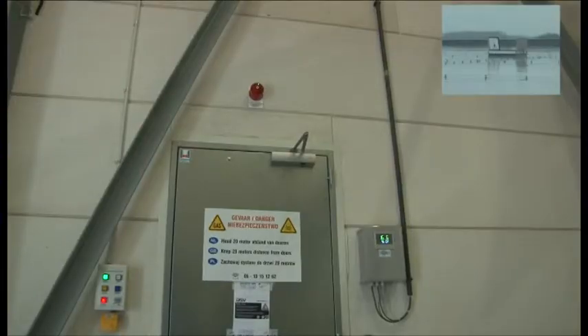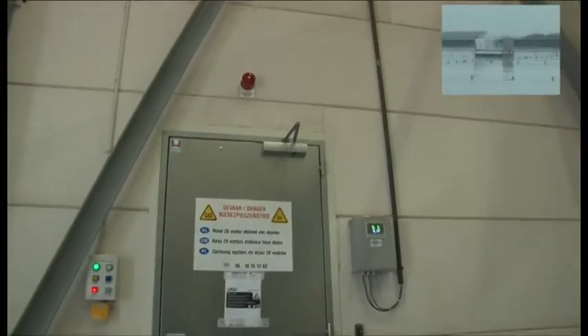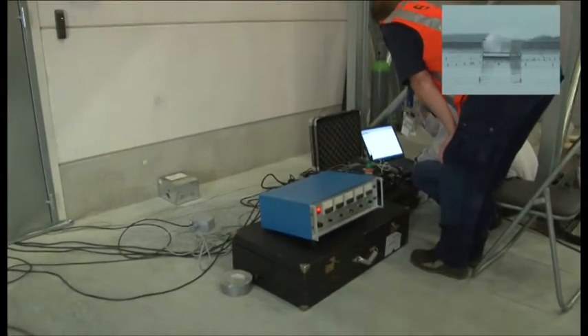The cameraman must also retreat. Outside the hall, the oxygen percentage is still between 16 and 17%, and it must go to 12%. Elsewhere, 14.1% is declared.